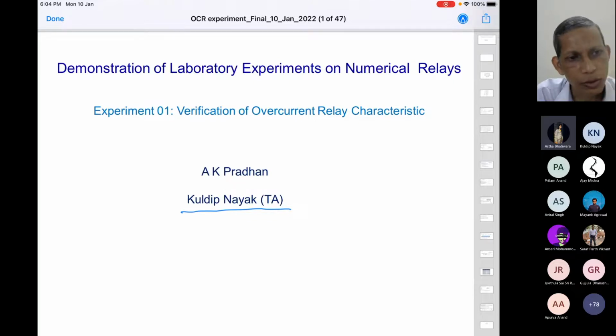So what we have done in this lab, to make it more realistic, is that we inject real current and voltages to the relays as per the requirement from the distribution side, and then we test the relays very close to the actual thing. Even in transformer protection, we'll see later on that we have a transformer and we are protecting it.